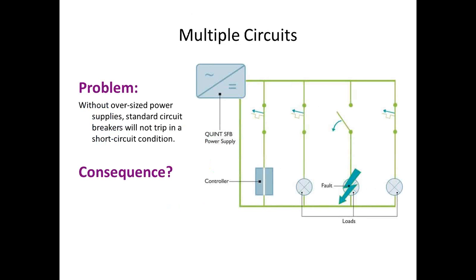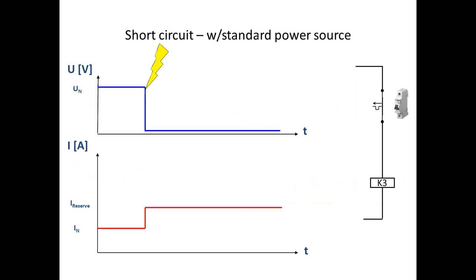The next concern involves power systems with multiple circuits. The power supply must be sized such that when a load experiences a short circuit, the breaker will trip. It's desirable for the breaker to trip fast enough to avoid a power glitch that can be seen on other circuits. This glitch can potentially reset the controller, or if the breaker does not trip, the controller will be off.